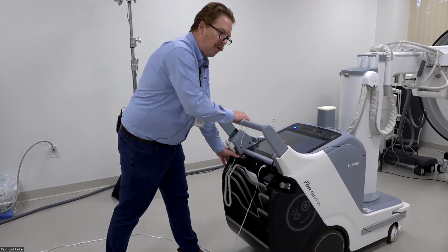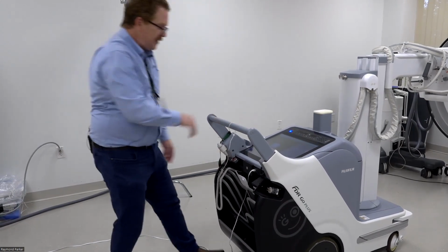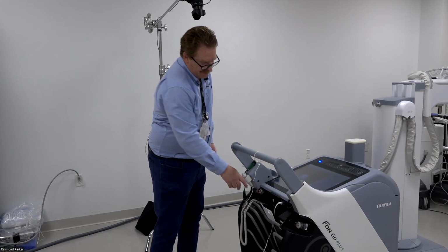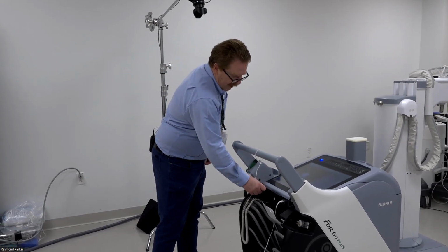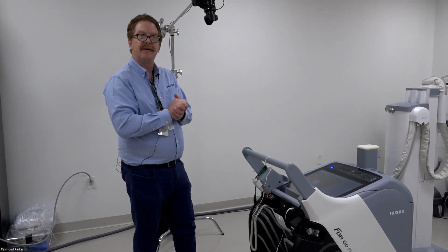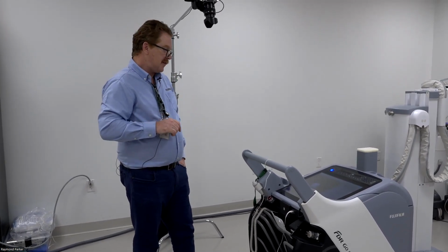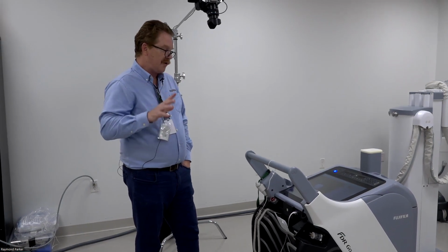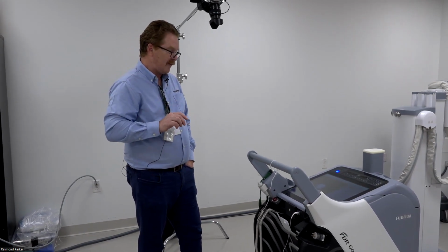When testing older platforms, this is one that I test every single portable I touch, especially the older ones. If the battery that supplies the emergency brake is dead, this unit will not do the emergency brake release. That should be changed during normal preventative maintenance.